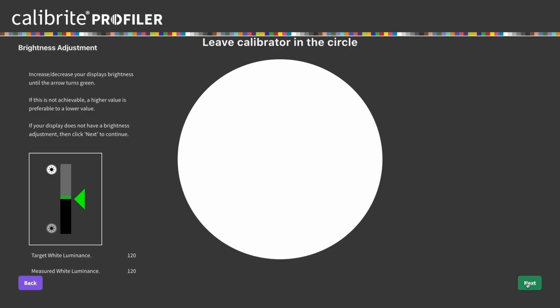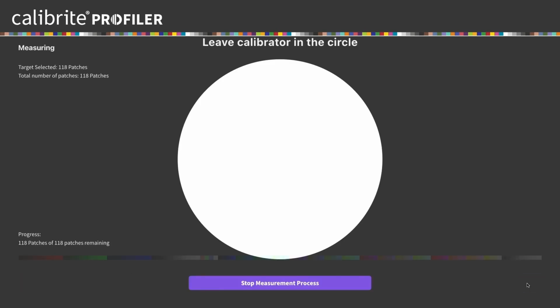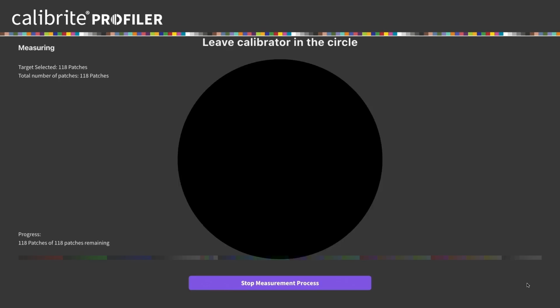Now this is the critical bit. We need to get the luminance correct. In fact, as you can see, it is set correctly. Important to mention, on a Mac, you can simply use the keyboard to decrease or increase the luminance level. On a PC, you'll very often actually have to use the controls on the base or the rear of the screen. Once we press next again, the device starts to measure.